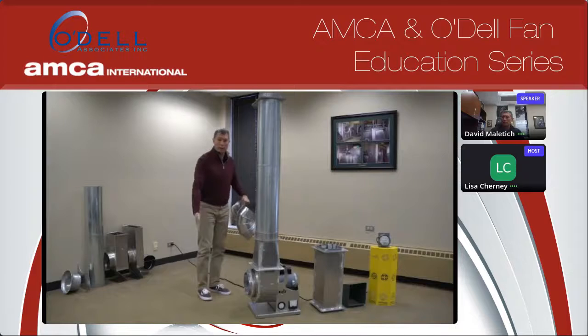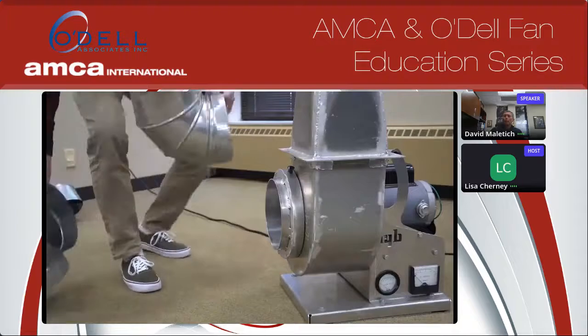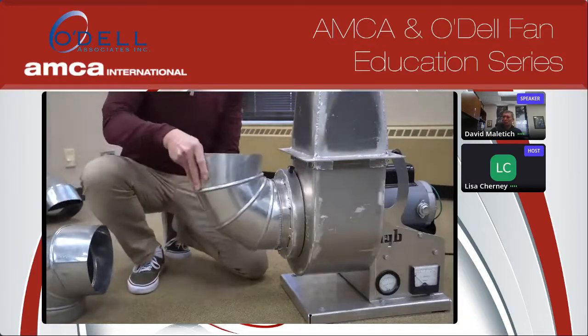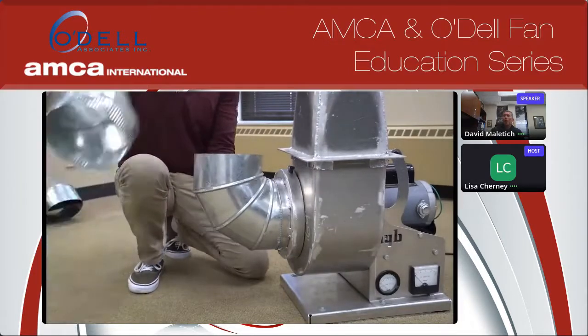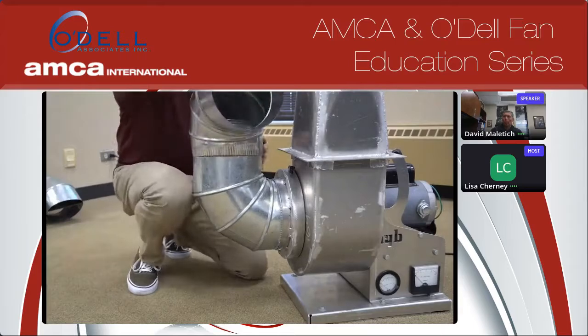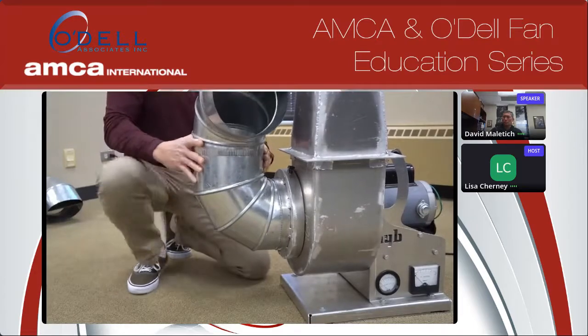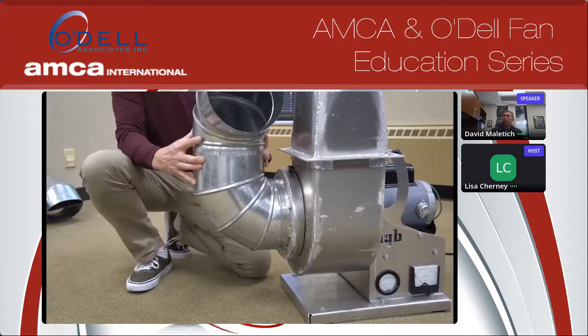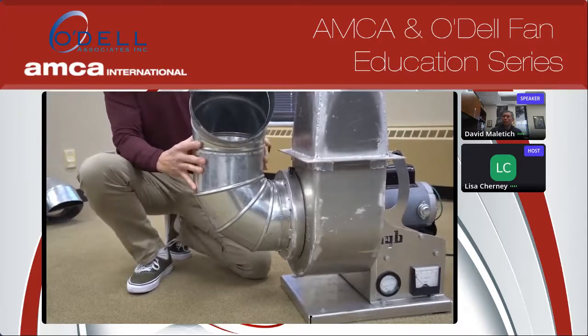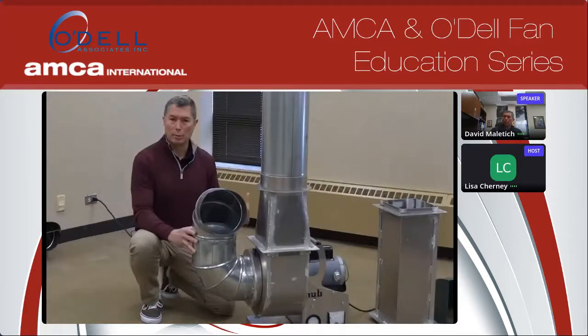Fans where you have a wall here, and so you don't have a whole lot of space in order to run ductwork into the fan. And what we're going to do is create a corkscrew and see how corkscrews affect the fan's performance. So put a 90-degree elbow on the inlet of the fan, and we're going to put it on in this direction here. Now basically, when you're looking at this, you have to also listen to it audibly because what you're going to hear is either the vibration and the fan noise go up or down.